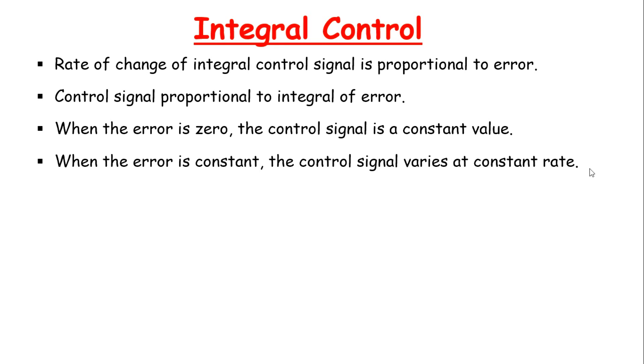So integral action is needed. Integral action is provided by summing the error over time, multiplying that sum by a gain, and adding the result to the present controller output. If the error makes random excursions above and below zero, the net sum will be zero, so the integral action will not contribute.